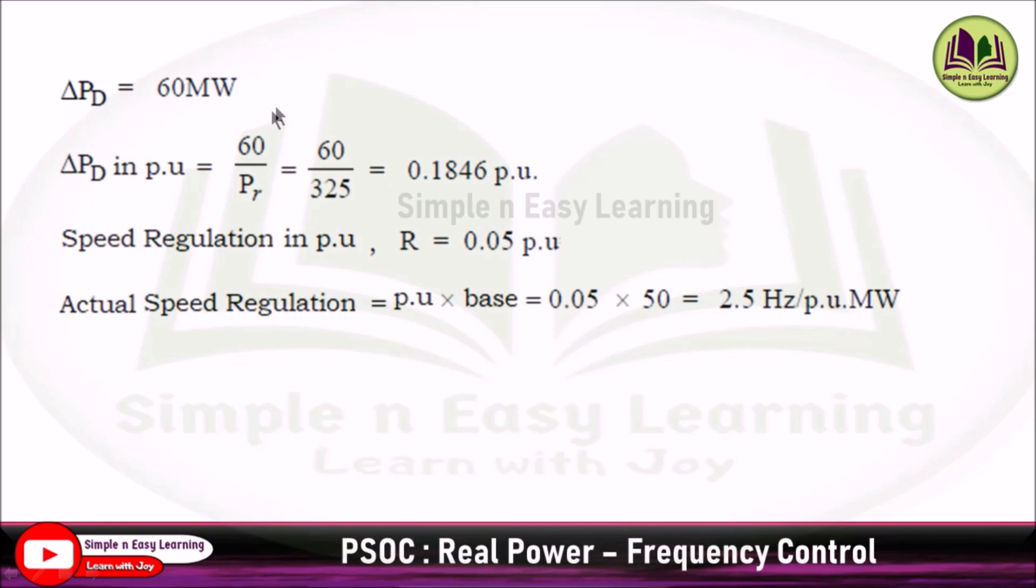The change in load is 60 megawatt. In per unit it is 60 divided by 325, that is 0.1846 per unit. Speed regulation in per unit R equals 0.05 per unit. Actual speed regulation is per unit value times base value, so 0.05 times 50, that gives you 2.5 hertz per per unit megawatt.